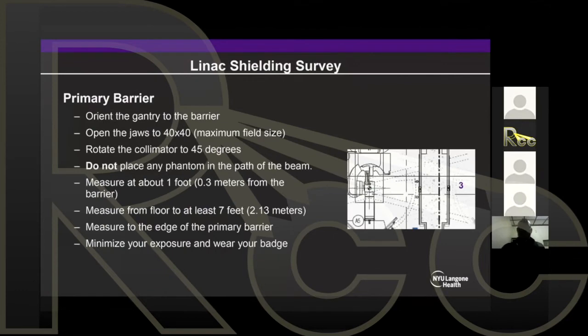And how you're gonna set up for the survey, right? So for primary barriers, and again, this goes back to we're gonna do it worst case scenario. So you're gonna orient the gantry to that barrier. So here we're gonna measure in this barrier, the area that we use the number 3. We're gonna open the jaws to the maximum field size, and we're gonna rotate the collimator to 45 degrees. So basically we're gonna try to cover as much as the machine could do, even if that's not really realistic, that's gonna be happening. But you need to make sure that in the worst case scenario it's working.